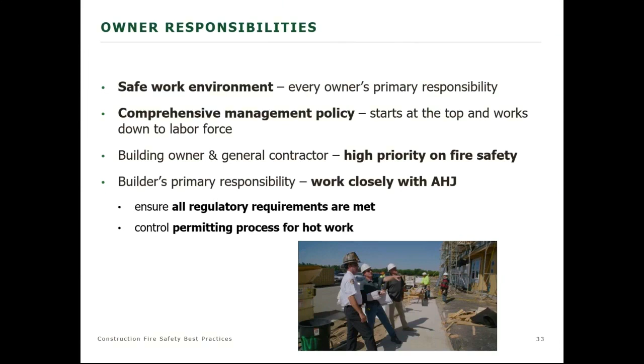I'm not going to read off every slide, but I'm going to read this one because it's important. NFPA 241 says a fire safety program shall be included in all construction, alteration, and demolition contracts. It is the right of the owner to administer and enforce this program, even if it is entirely under the jurisdiction of the contractor. So the owner, if they're not going to do it themselves, has to designate someone to be in charge of this program. Even if they delegate that responsibility to someone else, they can't delegate the accountability. So if there are code violations, it goes to the owner, even if the GC is completely in charge of it.